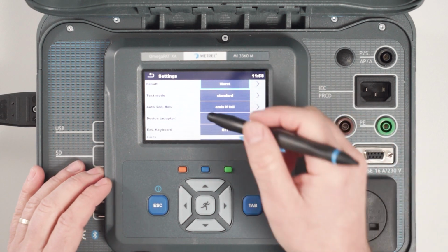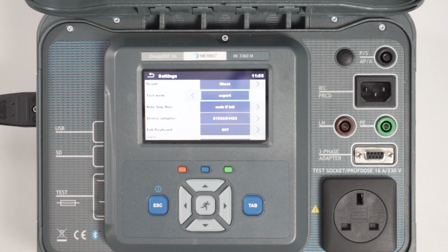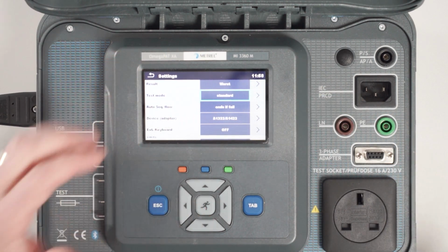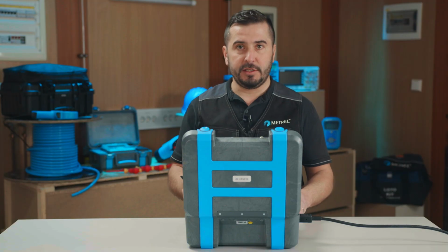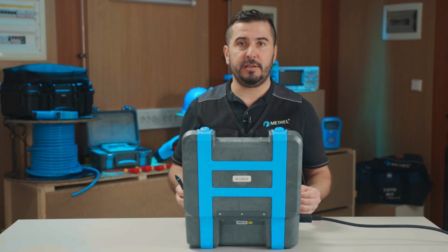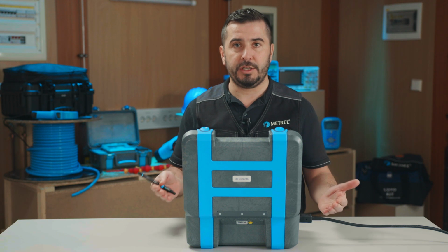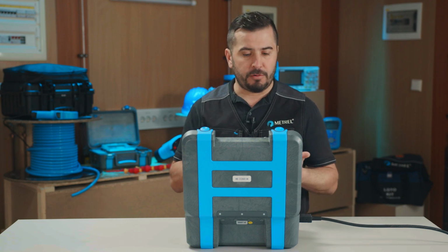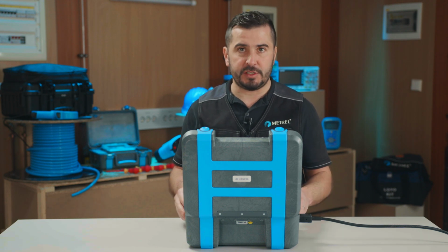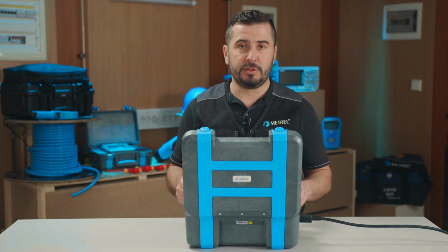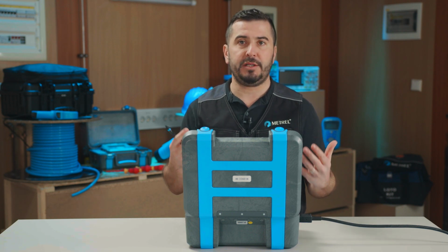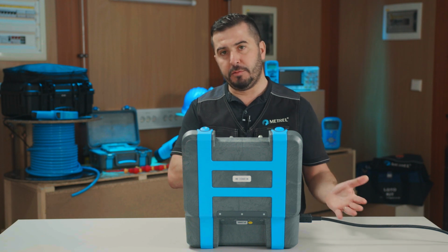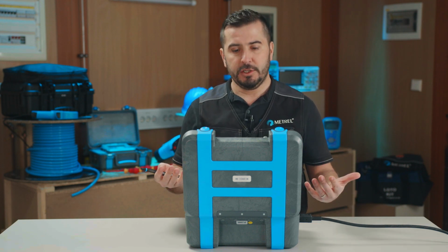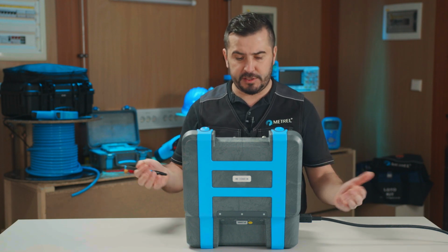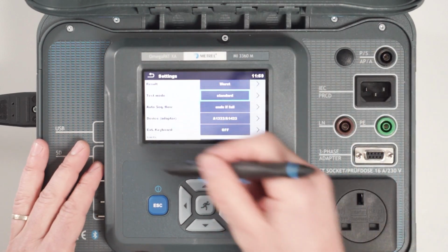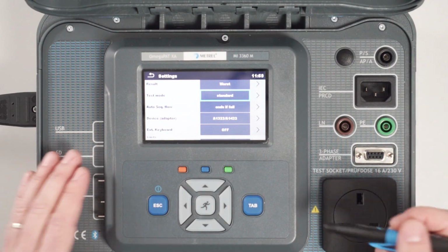We also have two different test modes, standard and expert. If we set instrument to expert mode, then at every single auto sequence where the visual or functional inspections are included, these two inspections will be automatically filled, and we will proceed automatically to the next measurement step. We can also set flow of the auto sequence itself.